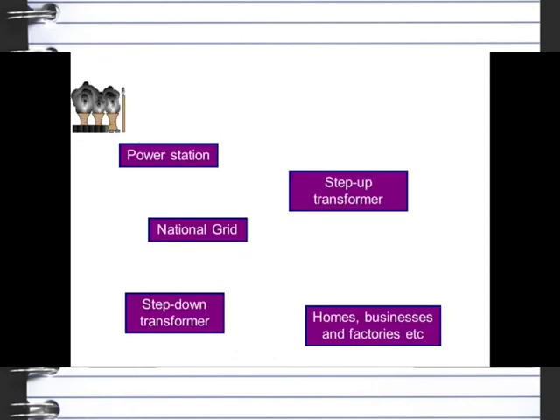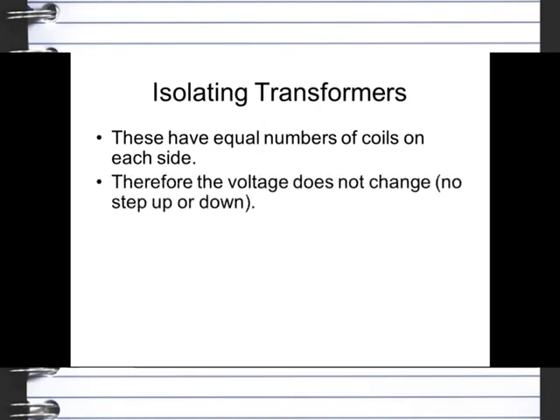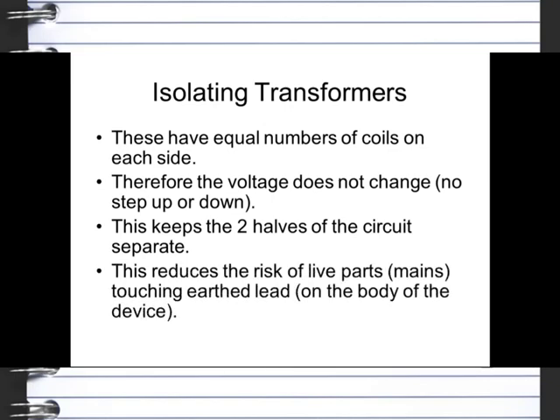Where are step-up transformers used? They're mainly used in the national grid, where you generate electricity in the power station. You go to the step-up transformer, which increases the voltage from around about 10,000 volts up to around about 100,000 volts. And then from the national grid, you go to a step-down transformer, which takes that 100,000 volts and steps it down to the 230 that we get in our home. Isolating transformers have equal number of coils on each side, so there's no change in the voltage with a step-up or a step-down. This means that you have two halves of the circuit, and they are kept separate. This reduces the risk of live parts, or the mains, touching an earth lead, and therefore affecting the body of the actual device.